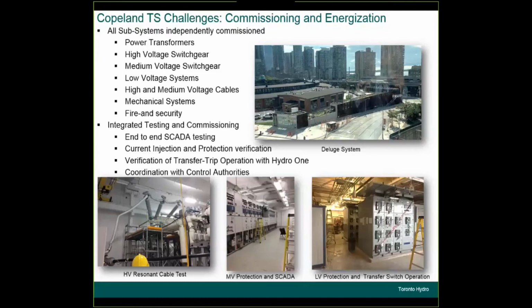We had all of our medium voltage protection in the SCADA communications that had to be tested, and then low voltage commissioning for our low voltage switchgear. We have a triple redundant station service room with 3 2,000 kVA transformers, each of which is capable of operating the entire station. 2 of them are fed internally from the Copeland medium voltage switchgear, and 1 is fed externally from our Esplanade transformer station.